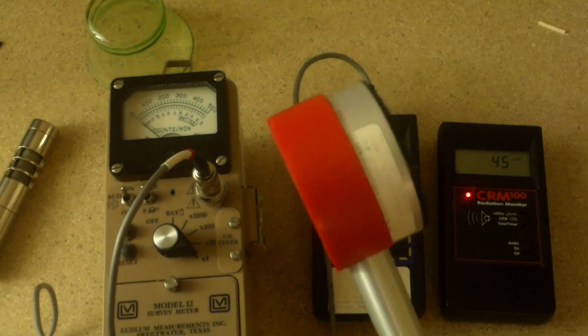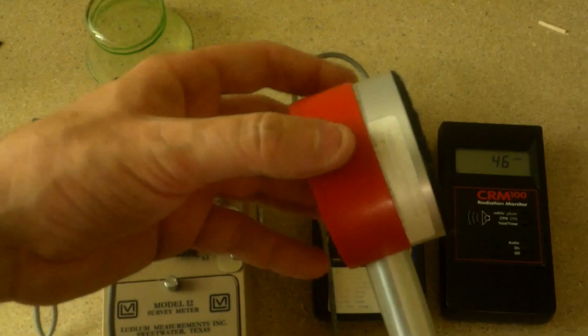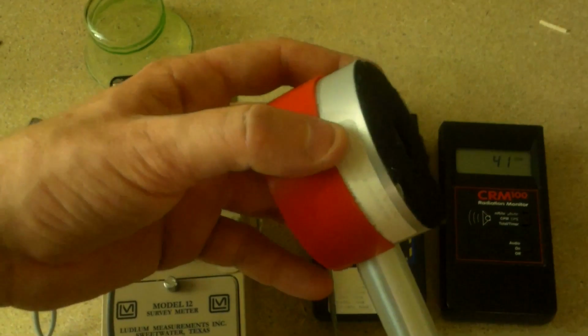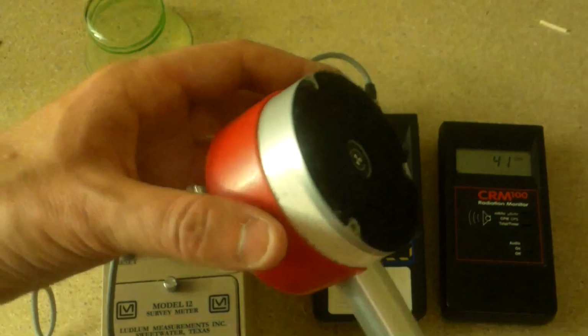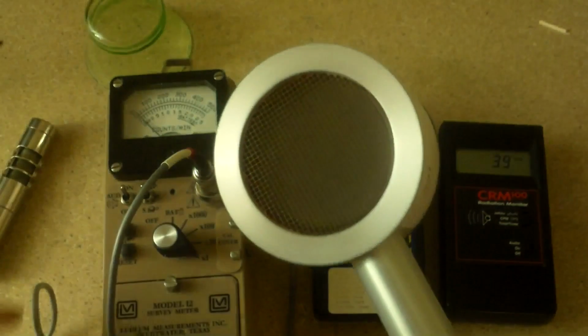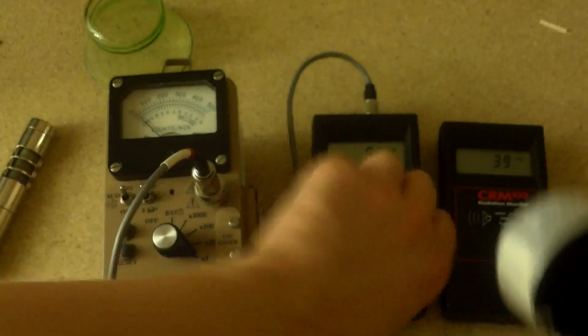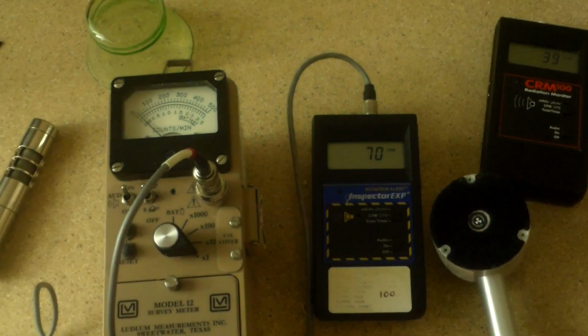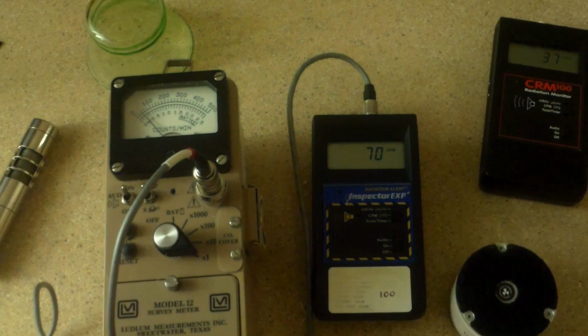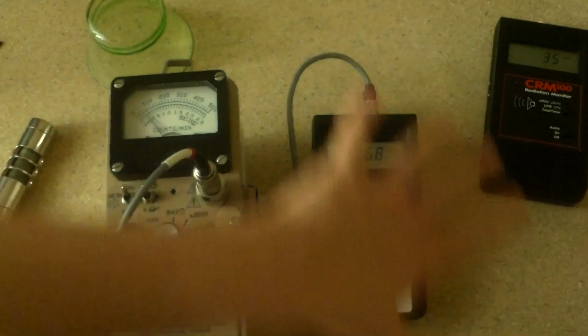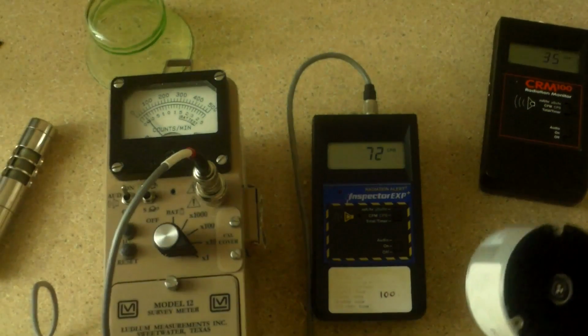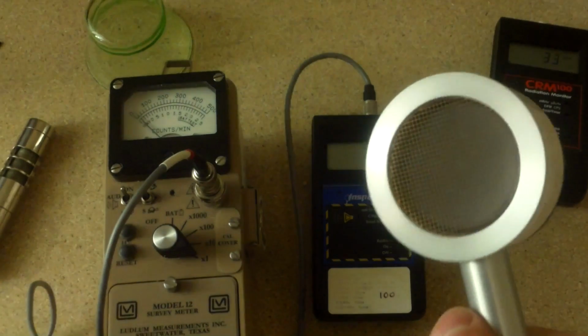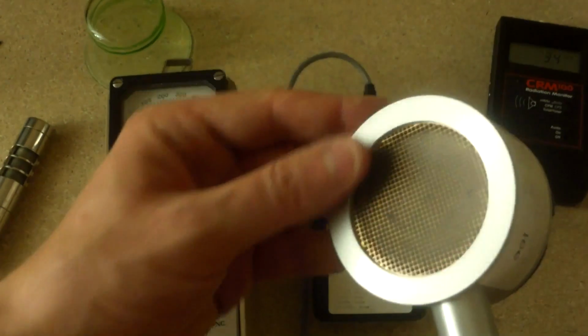Also, really, really low energy betas, like what comes from tritium, for example, and really, really, really weak X-rays can be detected with one of these detectors. So the benefit is you can do things like, for example, surface monitoring to look to see if there's surface contamination on an object, like alpha surface contamination. The downside to it, though, is you have this fragile window.